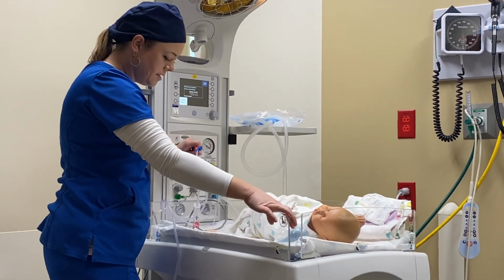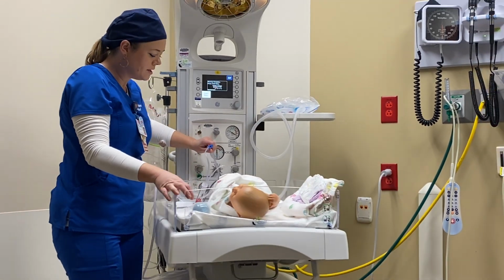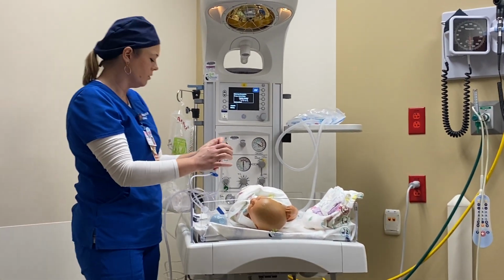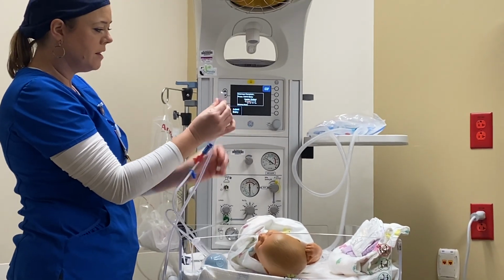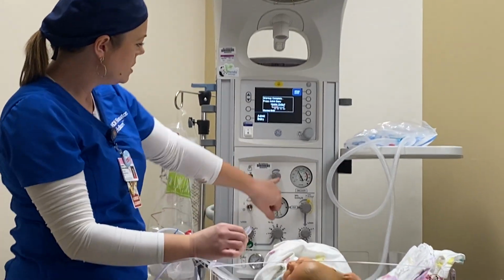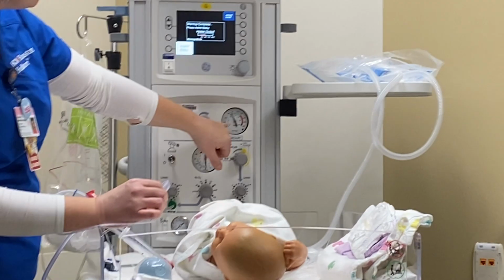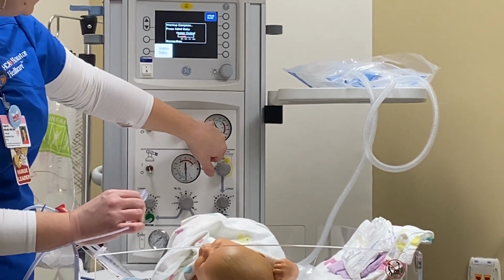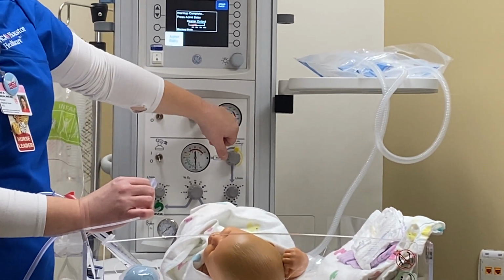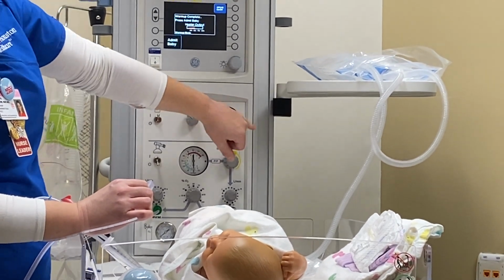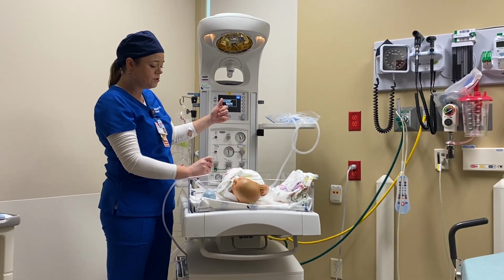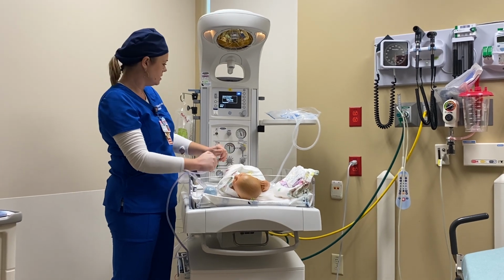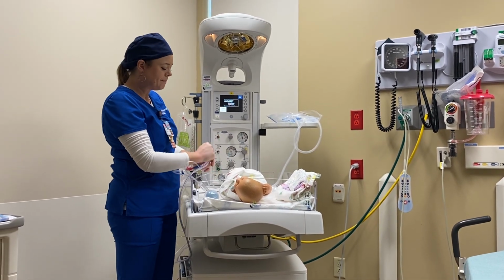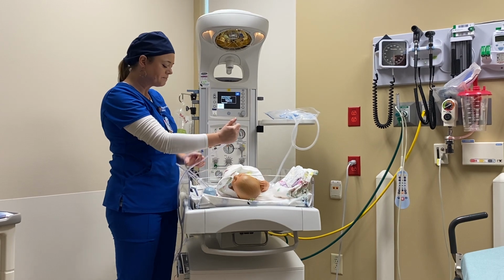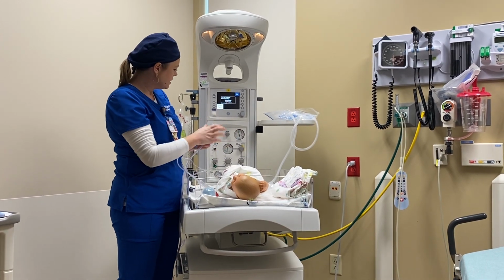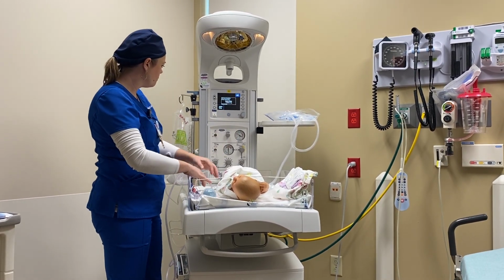Now I'm going to test the level of suction on my DeLee, because you can have too much or too little. So you want to bend the catheter in half to test your suction, and this is your suction barometer here, and you want it between, 60 is a tiny baby, and 80 is a normal size baby. You can go up to 120 if needed to achieve the suction goals that you're trying to achieve, if you're not getting what you need to get. But again, caution on a small baby. So once I know that my DeLee is working fine, okay, I've got that going for me.